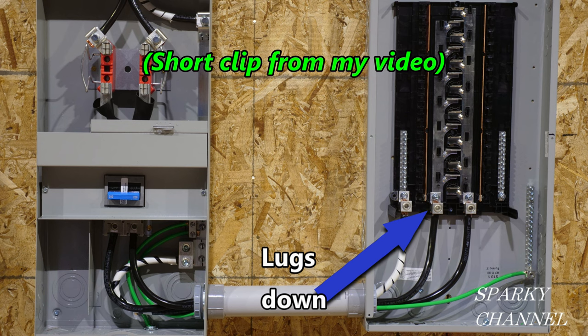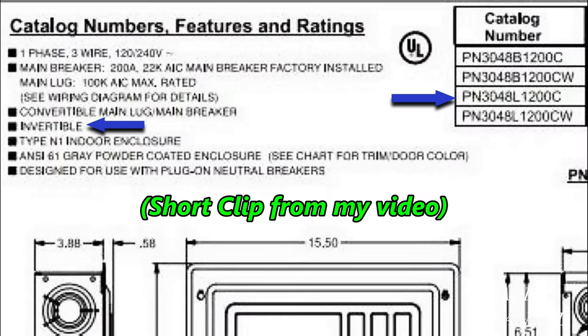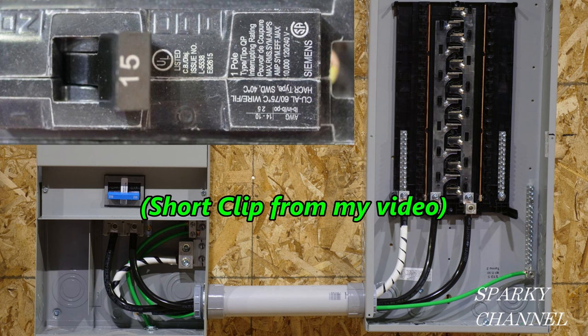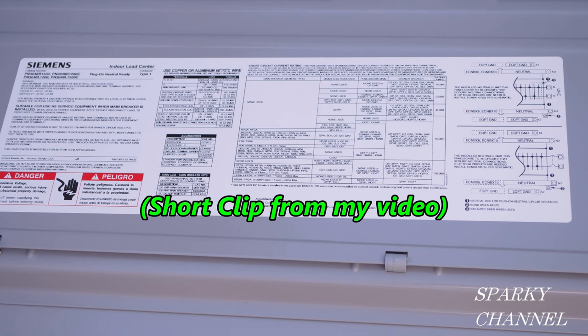Neither way is actually upside down because it's made to be installed either way. I'll show you some features of this invertible load center. First of all, it's listed by the manufacturer as being invertible. On this document found on the Siemens website, it states that this particular model number of load center is invertible. All the circuit breakers, including a main circuit breaker, if it's added later, turn on and off sideways. The main descriptive sticker is installed sideways on the back of the panel door.